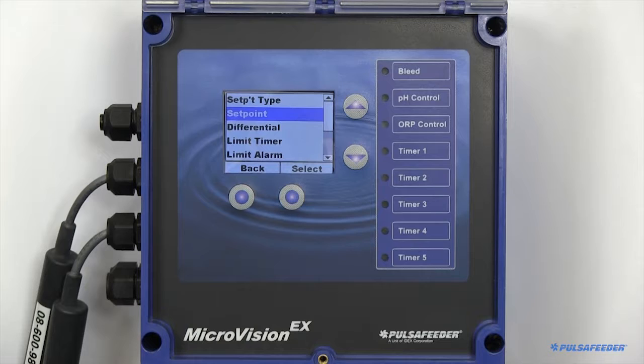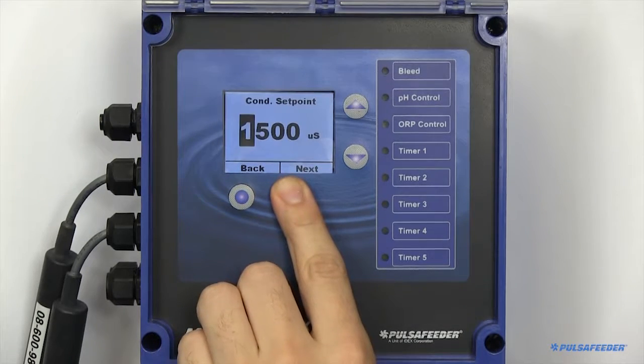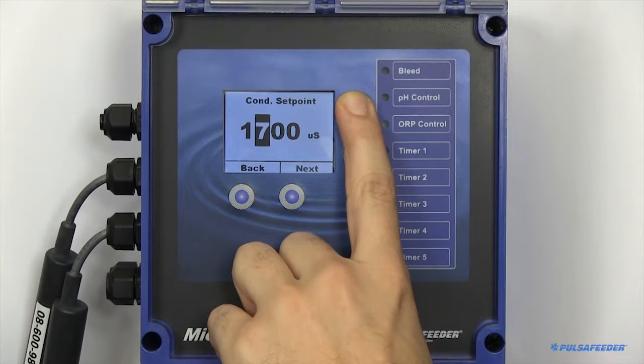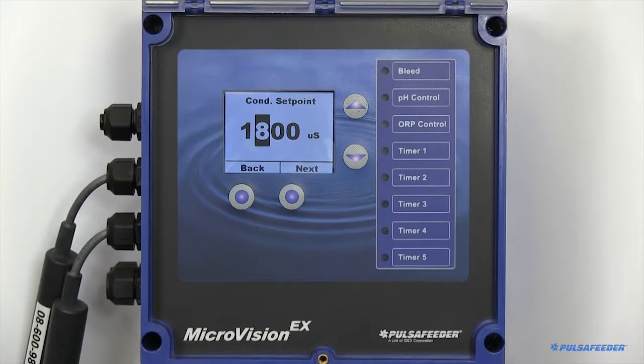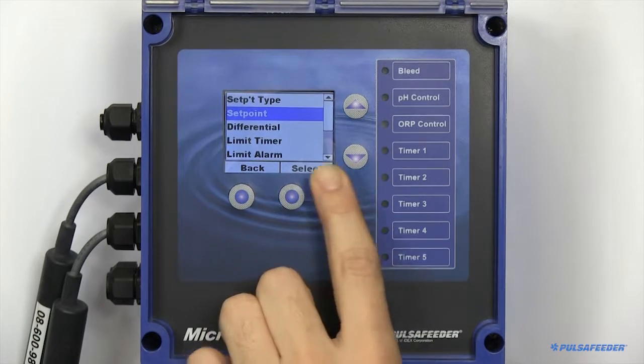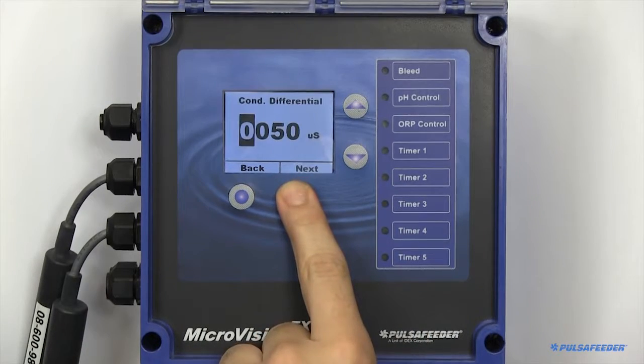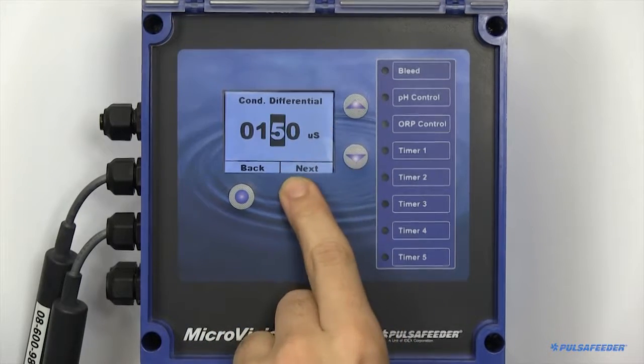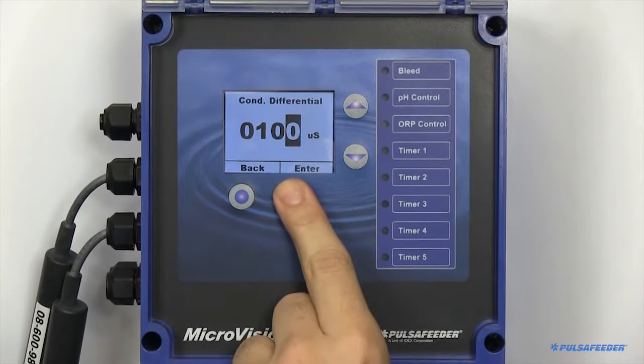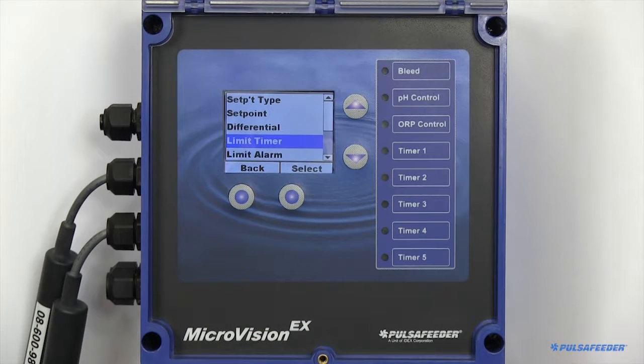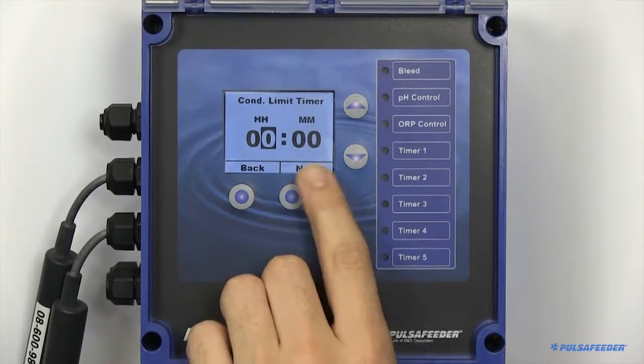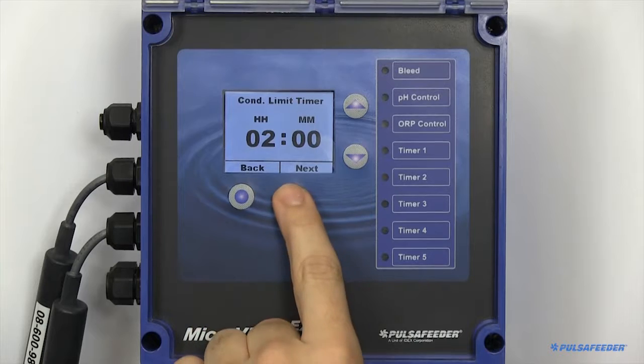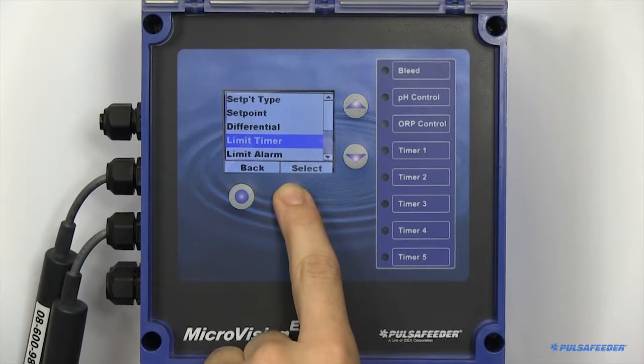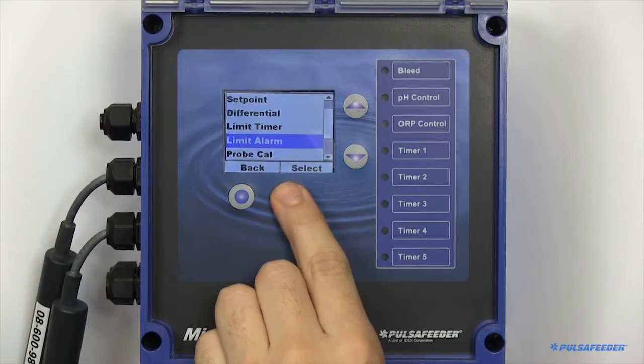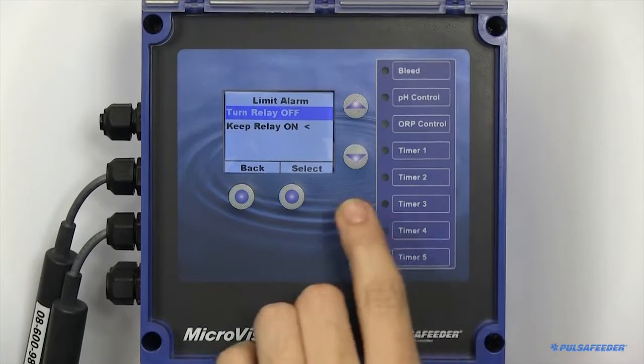Your set point is where the desired function will begin. The differential, or deadband, is the offset value which must be satisfied before the relay will turn off. Limit timers can also be enabled. The limit timer is the maximum amount of time you would like the relay to remain on until an alarm is triggered. You can set whether you would like the relay to remain on or turn off upon an alarm state triggering here.